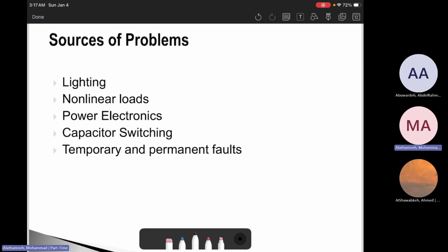The other thing, power electronics not only create harmonics, they can also be sensitive to sag transients. Power electronics are both cause and a victim, and I would say also the solver. So power electronics are the cause of power quality problems. At the same time, power electronics are the victim of the power quality problems. And at the same time as well, power electronics can be used to solve power quality problems. Those are the cause, the victim, and the saver. But we need to make sure to make a proper usage for them. That's the thing.